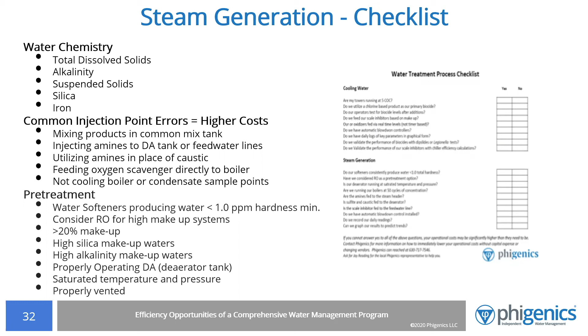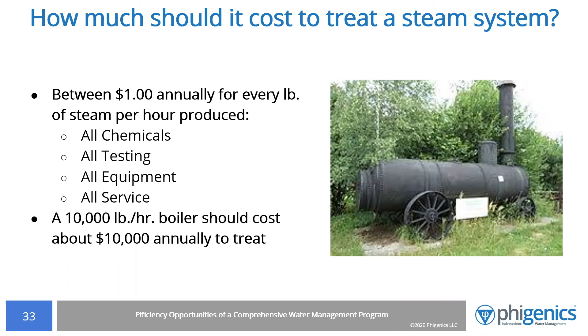So how much should it cost to treat a steam system? It should cost about $1 annually for every pound of steam per hour produced for all chemicals, testing, equipment, and service. So for a 10,000 pound per hour boiler, it should cost about $10,000 annually to treat the water. Again, this can vary from region to region, but if you're not tracking this number, you really don't know where you are.